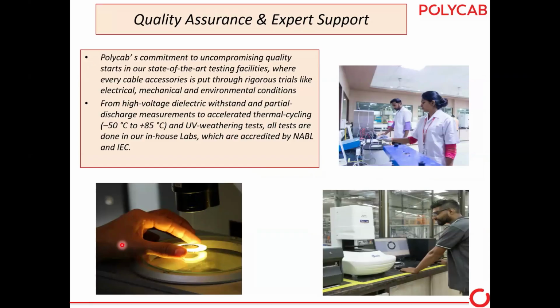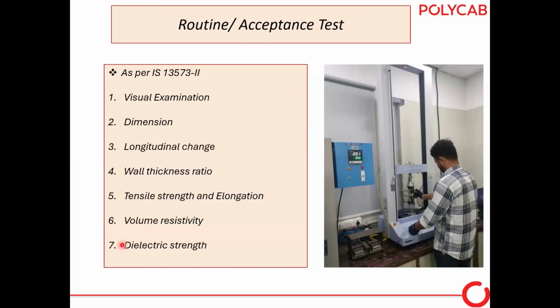As we are manufacturing cables and cable accessories in-house, and cables from low voltage to extra high voltage up to 220 kV, we have a very expert technical team, and the same technical expert team works for the cable accessories also. We have all the facility of testing and quality. Whatever the IS standard says, as per IS 13573, we do all the testing in-house: visual examination, dimensions, longitudinal change, wall thickness ratio, tensile strength, volume resistance, dielectric. Everything is in-house.